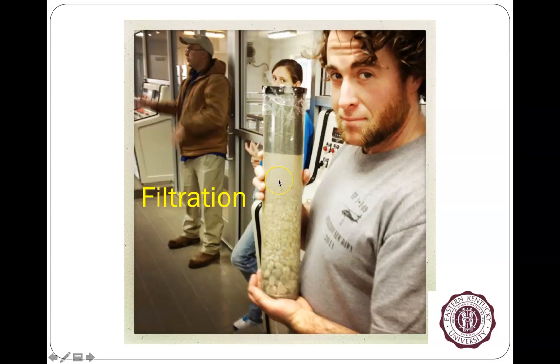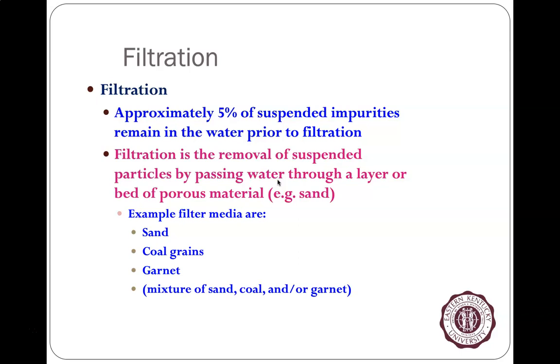This style is very common at a conventional water plant. Filtration removes approximately five percent of remaining suspended particles, and often it involves removing the particles by putting them through some sort of porous material. Sometimes it's manufactured filters, but in many cases it's traditional bank filtration — passing the water through a layer of porous material such as sand, coal grains, or garnet.